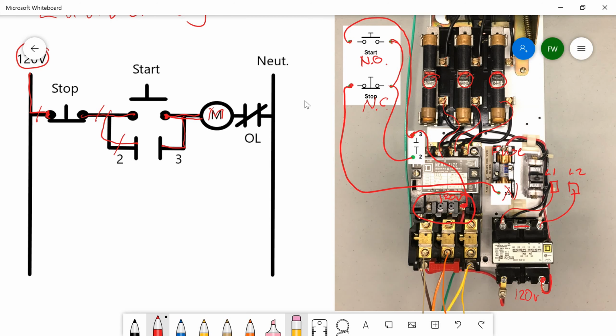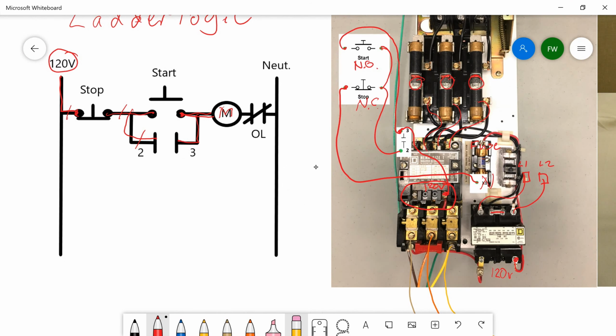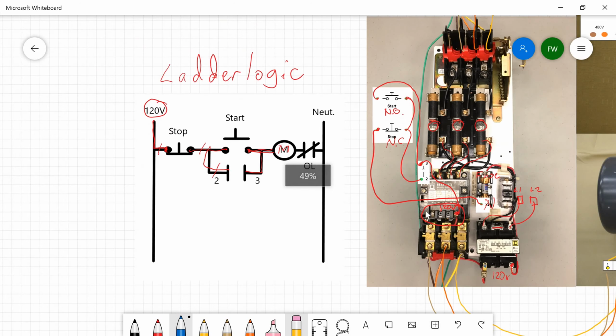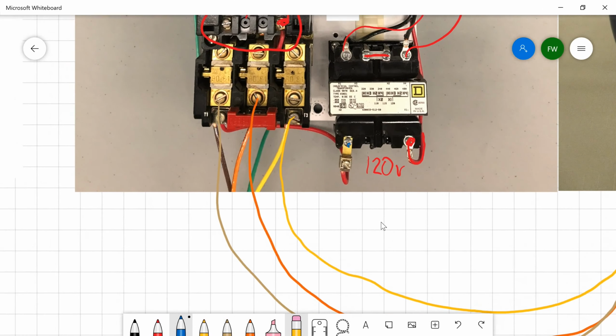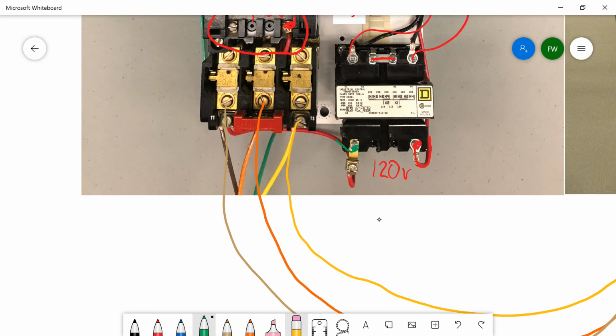We're left with the neutral. The neutral in this particular case is coming off of the other side of the control transformer, and you can tell that it's on the other side of the control transformer because you'll see that it's grounded to the case of the frame. One of the most common mistakes I see is that people forget that on any 120 volt control transformer, on the other side, you're going to take that and ground it to the case. That's almost exactly what they refer to as the system bonding jumper, and that's on your three-phase transformer. In this particular case it is a single-phase transformer. If you're above 50 volts, you need to bond your secondary to the case.